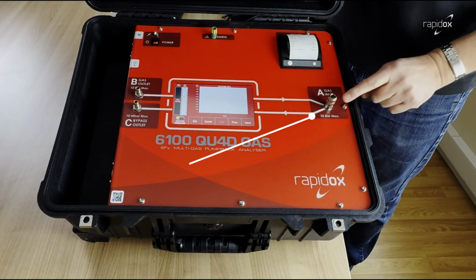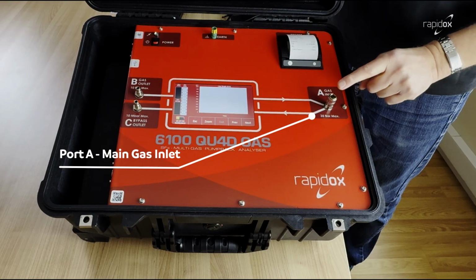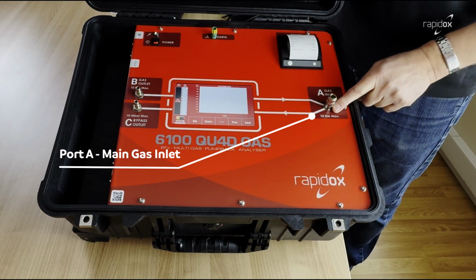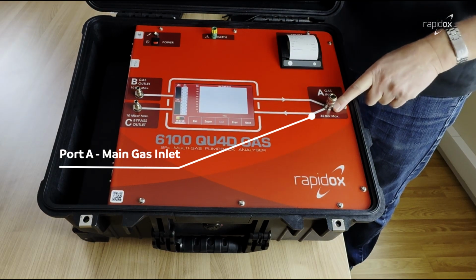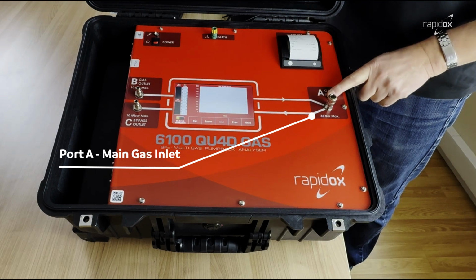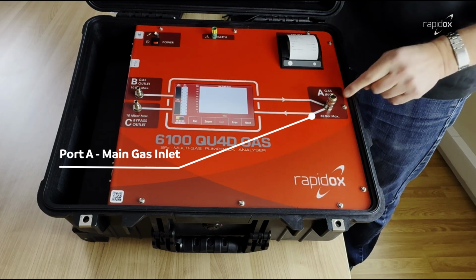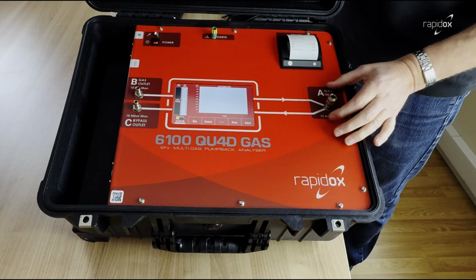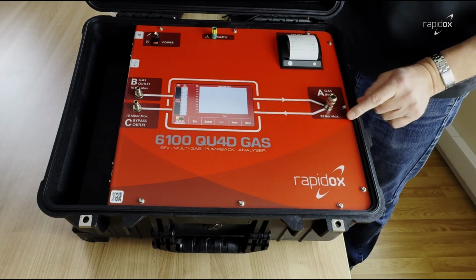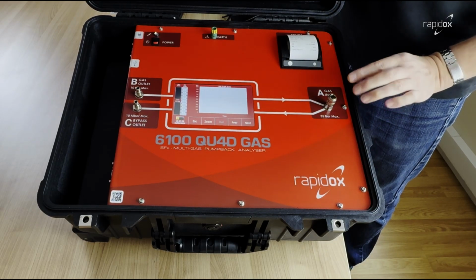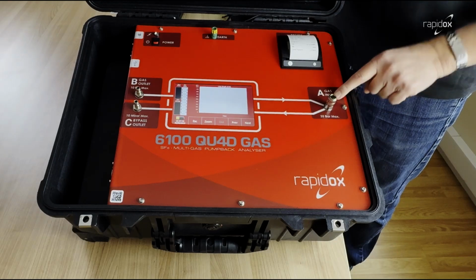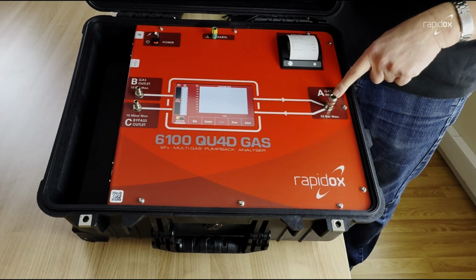Over here we have the main gas inlet. This is where the main hose is attached to do a test from a GIS, a gas insulated circuit breaker, and that's where gas up to 35 bar can be attached. So this is the main place where the analyzer is used to do sampling.